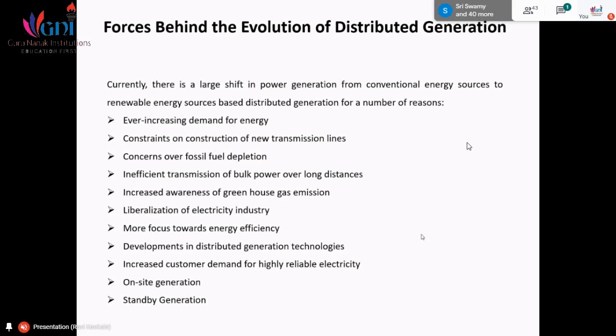Why are we moving toward higher voltage for transmission? Because if you increase the voltage level to transmit a bulk amount of power from one location to another, the current value required will be lower. If the magnitude of current is lower, the I square R losses will be reduced. That's why we are moving toward high voltage transmission.